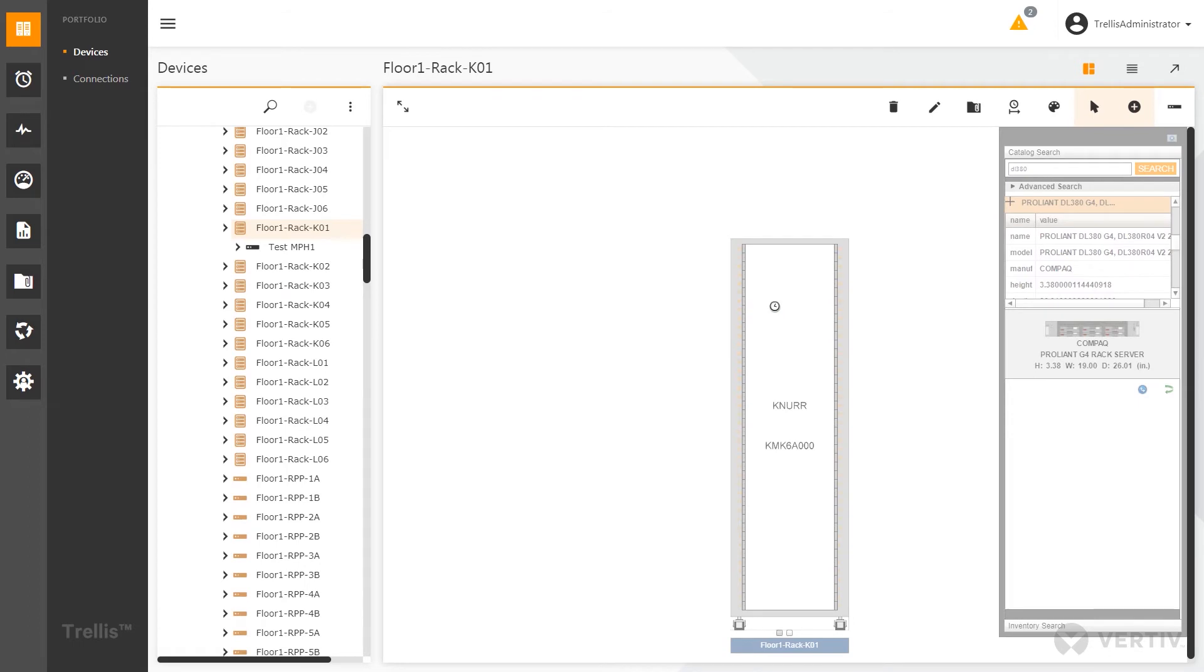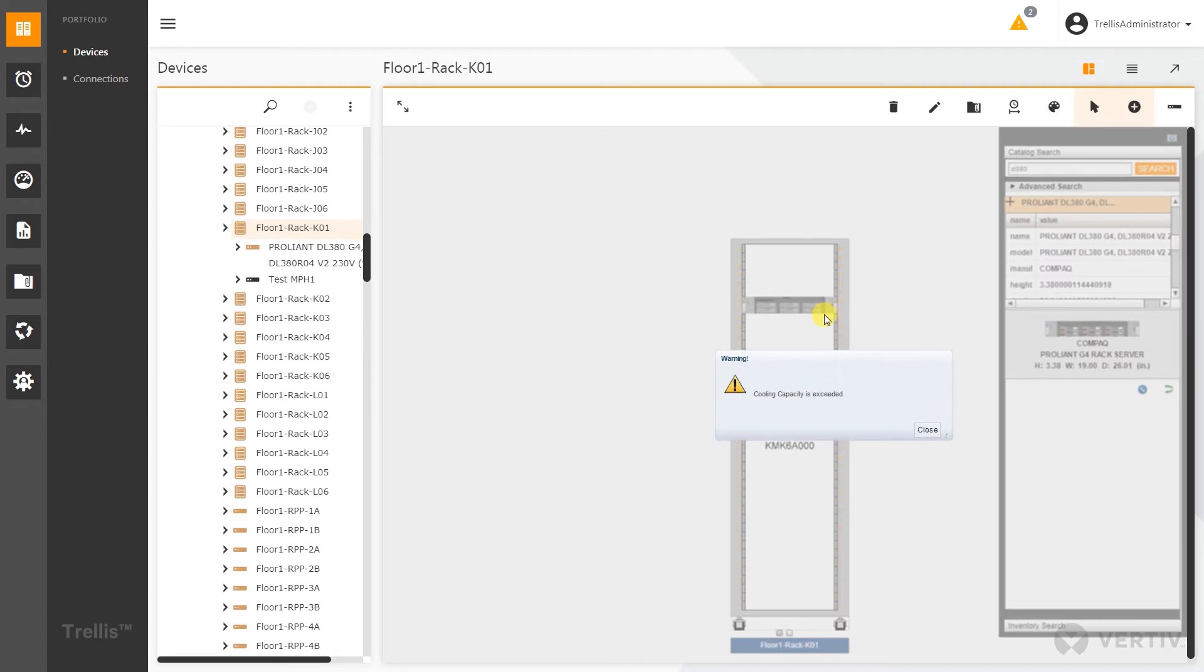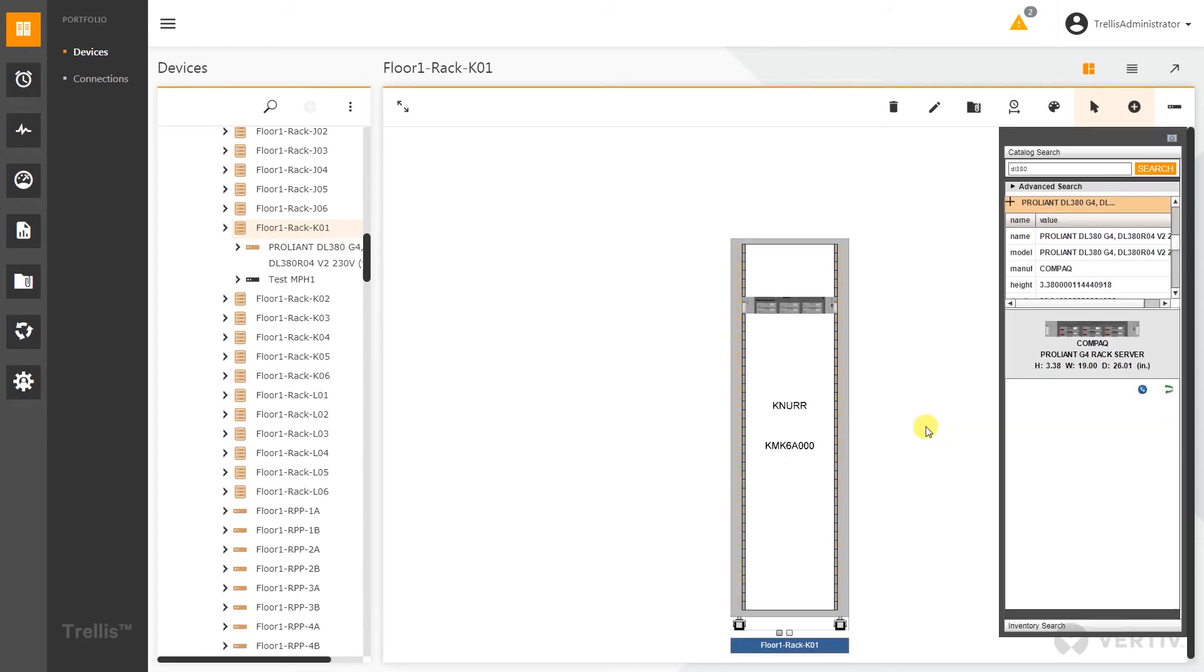I can just simply drag and drop that into U35. As soon as I release that mouse button, it's going to place it. Just in the past when we had different capacities that would be set up, different thresholds, we can see here that my cooling capacity is exceeded. But again, I can just abort that and hit close and allow me to still place that in there.